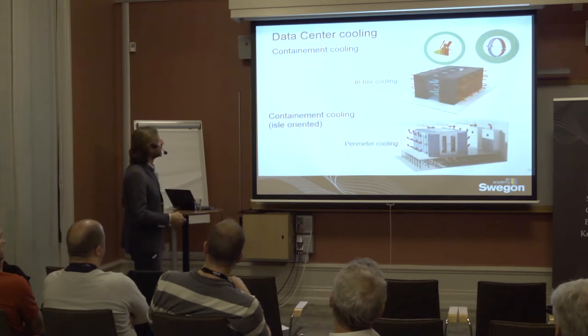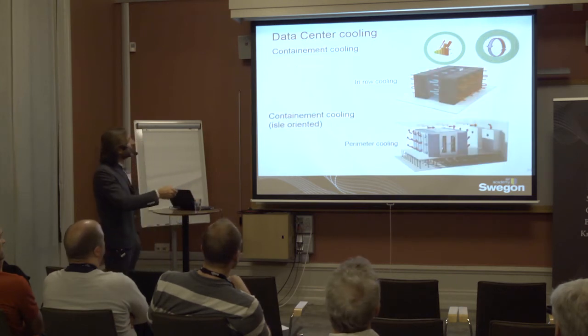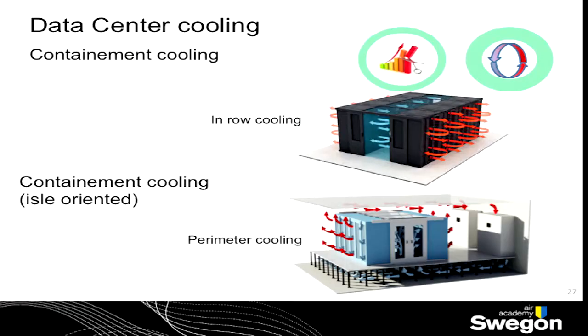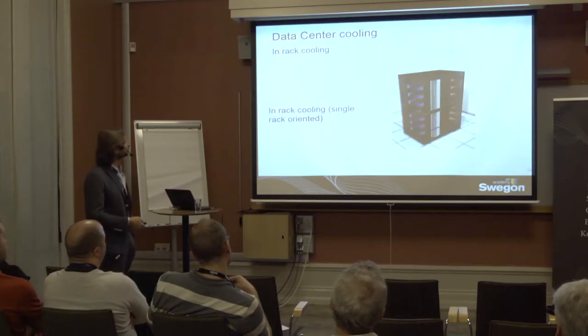Okay. Going deeper, you find the containment cooling. We will go deeper on this because it is very interesting. It is both for in-row and for perimeter cooling. As someone of you asked before, it is a technology that can be combined with both in-row and perimeter. And in this way, we avoid the false floor and the pressure losses connected with it.